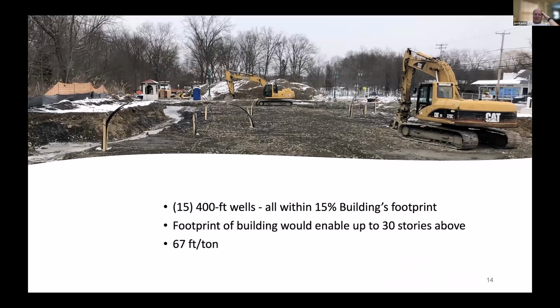We put in a geosystem for this. You can see here, these are 15 400-foot wells. They occupy only about 15% of the building footprint. That was enough for the whole building. If we maximized the entire footprint here, we would probably have enough room for a 30-story building. I would argue even nowadays a little bit more, from what we learned here from that building. The loop field is about 67 feet per installed ton, so you can see we're pushing the conventional wisdom of how many feet per ton we need.